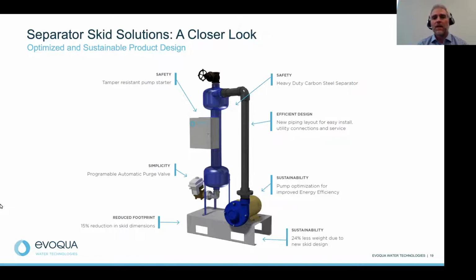Let's look a little bit deeper inside the overall offering. This technology obviously comes in both skidded and non-skidded scenarios. We even have various different recovery vessels, reducing your solids loading discharge. But again, recently, Evoqua made an investment into optimizing the design to really bring down costs, bring down footprint, and improve the sustainability of the overall offering. We've chosen tamper-resistant starters, really focusing on safety, efficient layout of our piping, and simplicity of the automatic purge valve. But a lot of optimization was focused on reducing footprint, a 15% reduction in footprint, but also weight. We want to make sure this product can be fit and utilized in various tight utility rooms or the continually shrinking amount of available space in your cooling tower environment.